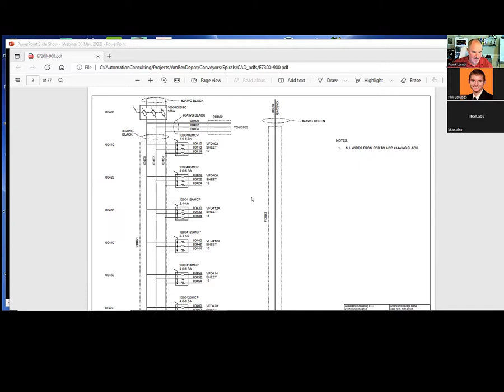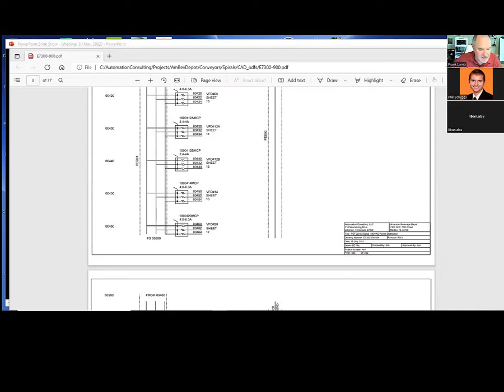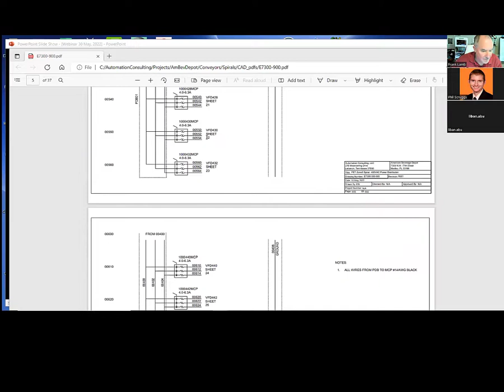So like I said, I started this drawing on May 16th. I think this particular drawing probably says, let's see, 18 May. So I completed it and dated it as of that date. There's a continuation, power distribution block 1, power distribution block 2, and a lot of this had to be sized, right? So all these motor circuit protectors, these are manual. They have overloads built into them, and you can turn them off. So this removes power from the drives, and it disconnects itself if there's an overload of some kind. So that's a little of the 480.